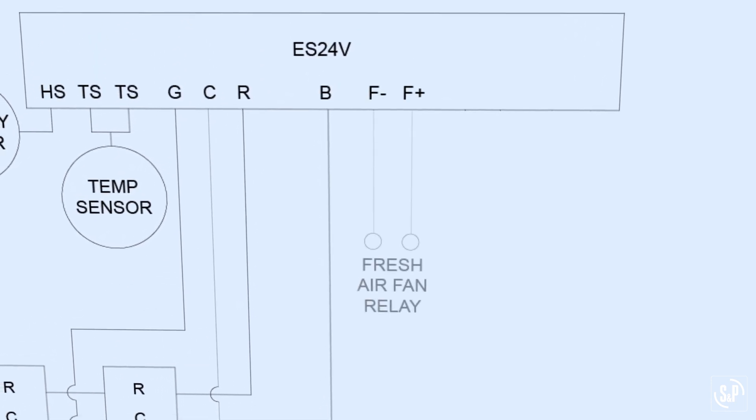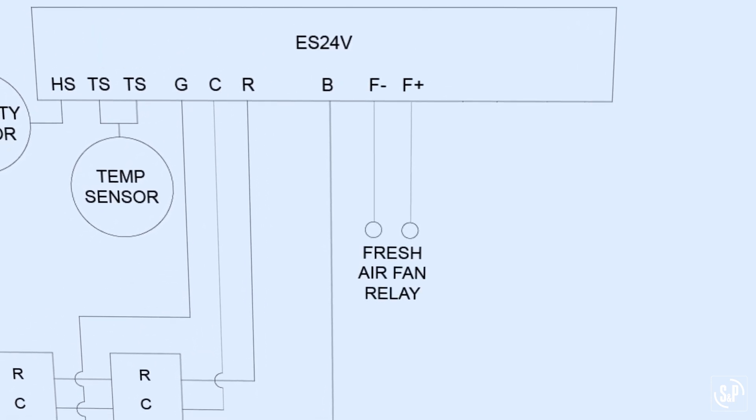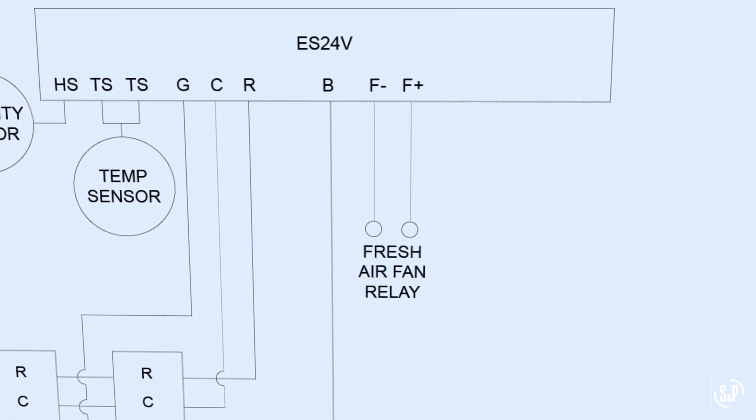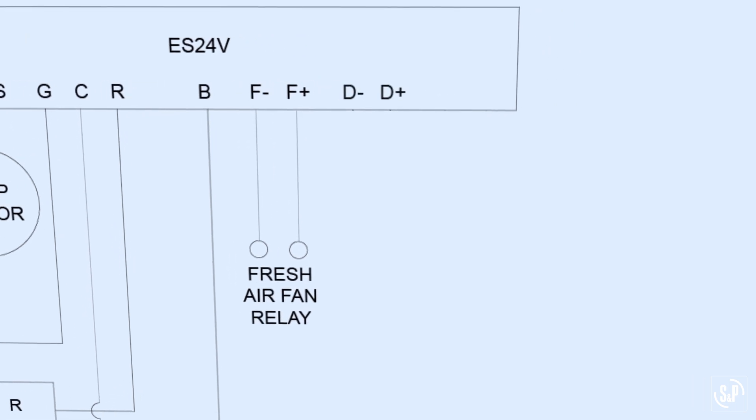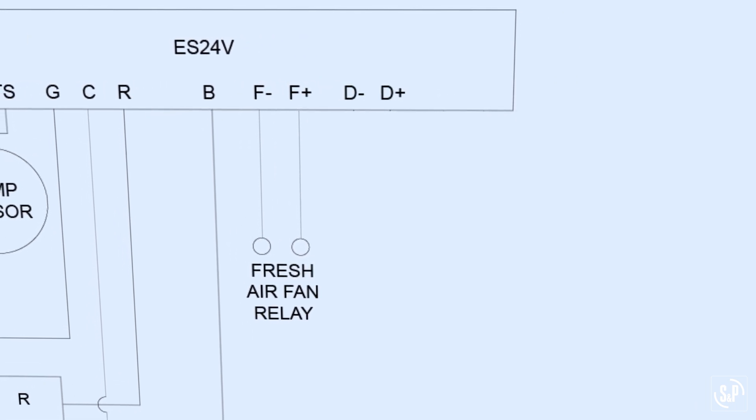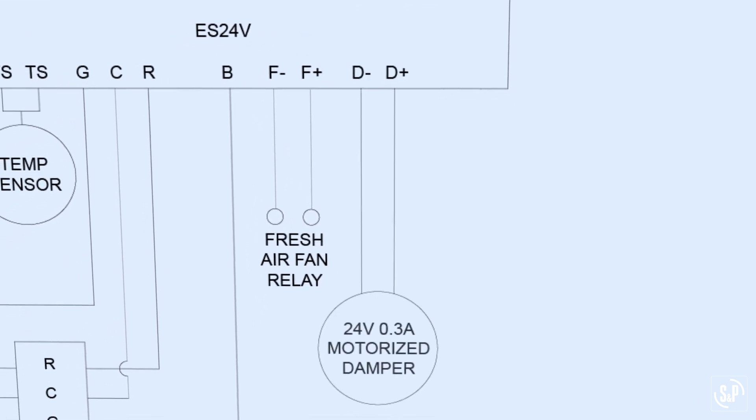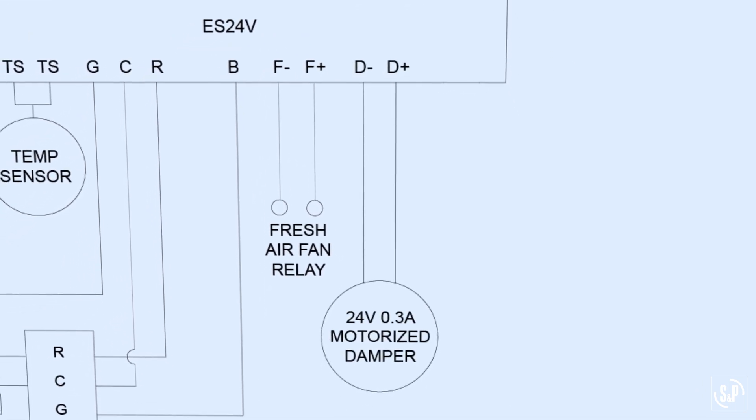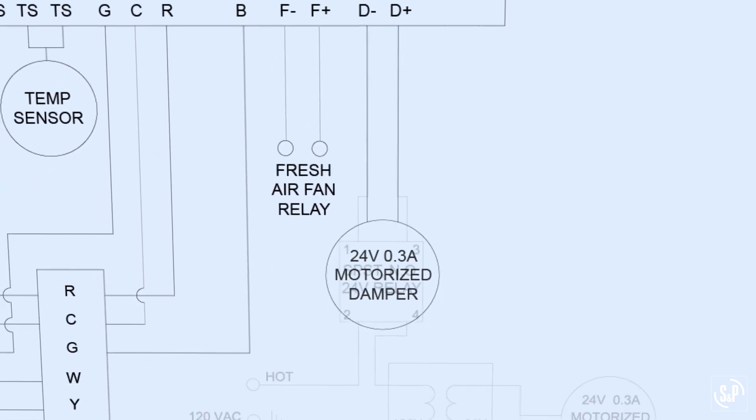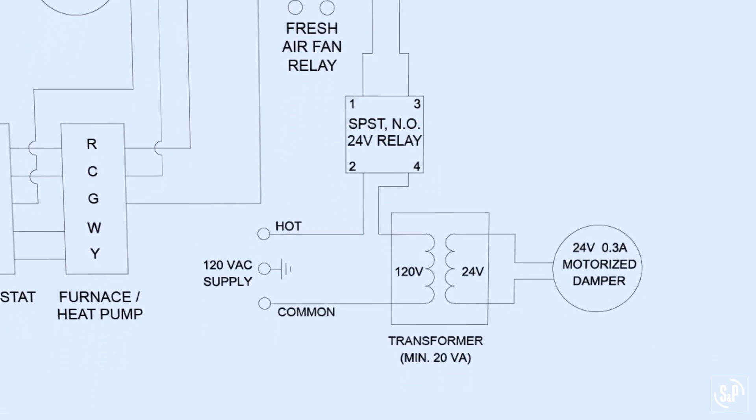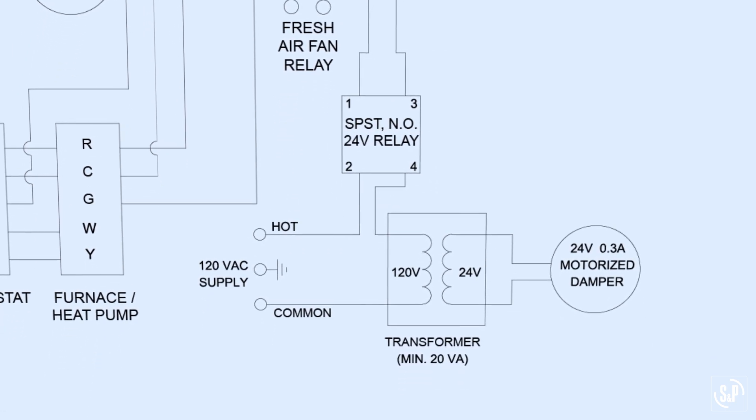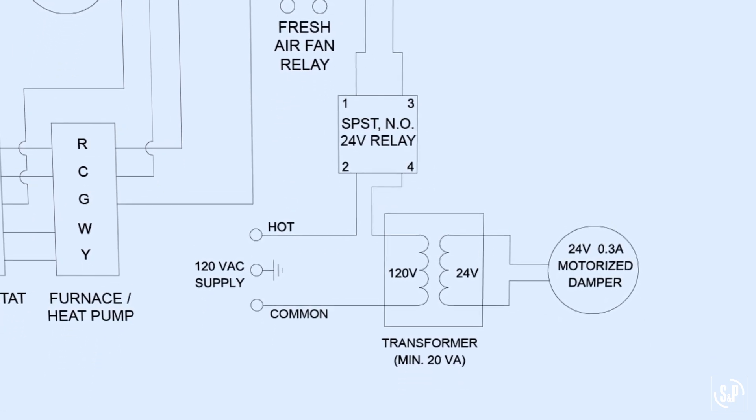The F negative and F positive terminals connect the ES24V to the fresh air supply fan relay. The D negative and D positive terminals connect the ES24V to the motorized damper or motorized damper relay depending on the available apparent power of the HVAC transformer.